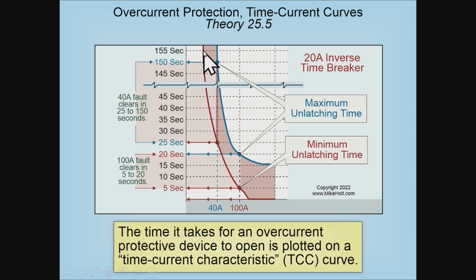The red line indicates the minimum time it's going to take to unlatch that circuit breaker, because you taught us about latching. So 40 amps goes over here. It says, well, you know what? Because of the bimetal, it could unlatch in about 25 seconds, but it might not. Then you go up a little higher on this 40 amps on a 20 amp breaker, and it might take 150 seconds. Is that 2.5 minutes? 150? Yep, 2.5 minutes.